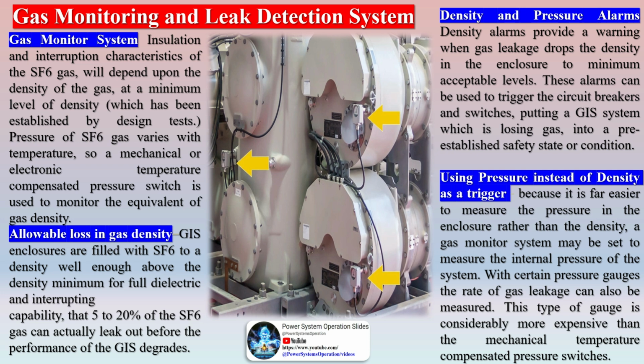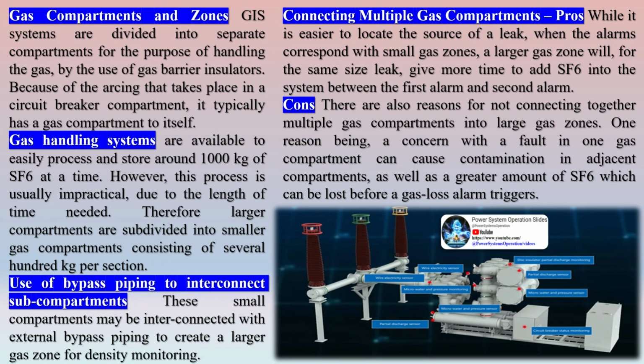Allowable loss in gas density. GIS enclosures are filled with SF6 to a density well enough above the density minimum for full dielectric and interrupting capability, that 5 to 20% of the SF6 gas can actually leak out before the performance of the GIS degrades.